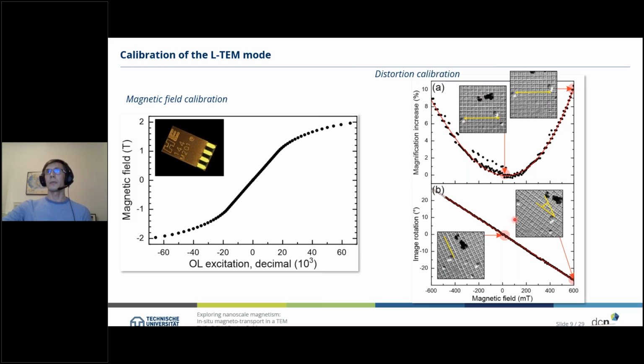Another thing we need to take care of is a variation in the magnification of our image. You can see that by looking at that cross-grating, which we used here for calibration: the distance is different for 0 magnetic field as compared to 600 milli-Tesla. The spacing gets larger and we have an increase of magnification in the order of up to 10%. But since we calibrated that as a function of the magnetic field, that can also be used for rescaling the images in post-processing.